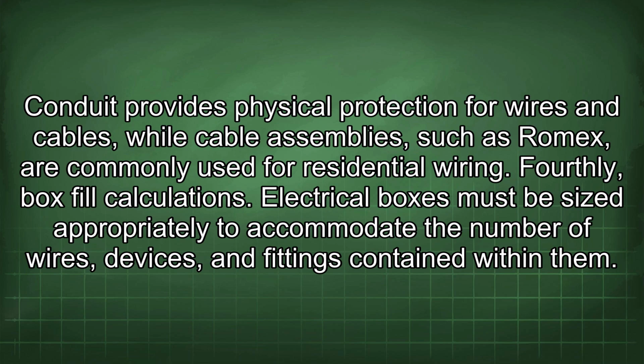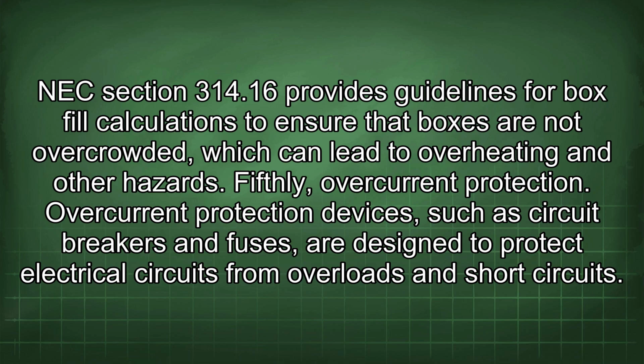Fourthly, box fill calculations. Electrical boxes must be sized appropriately to accommodate the number of wires, devices, and fittings contained within them. NEC Section 314.16 provides guidelines for box fill calculations to ensure that boxes are not overcrowded, which can lead to overheating and other hazards.